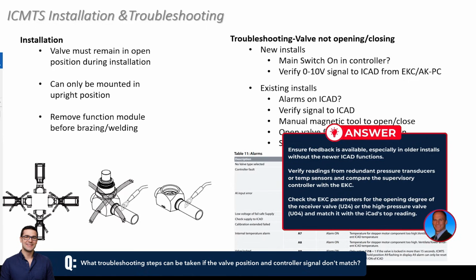So normally either we're looking at something where there's redundant pressure transducers or temp sensors, and if somebody's looking at the one that's tied back into a supervisory controller, then we need to make sure they're also looking at that same reading in the EKC, because there's obviously the chance that they're different, and so what they think they're seeing isn't what is actually going on inside the controller.